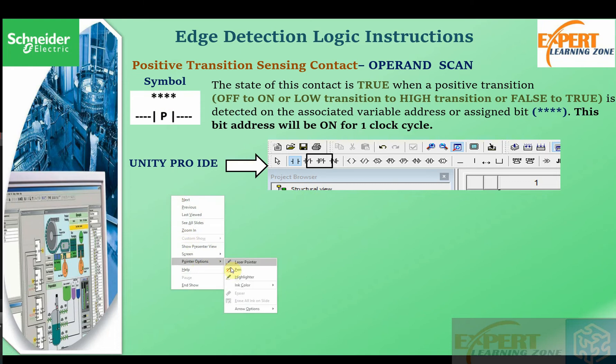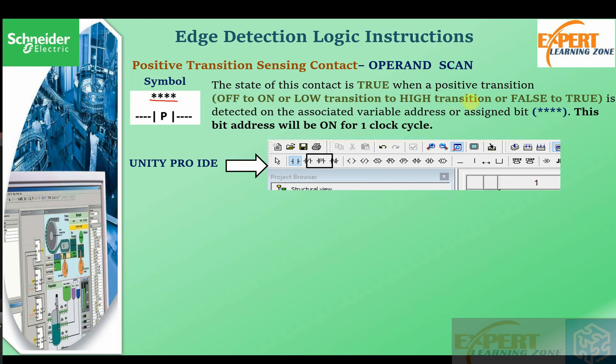To begin, we start with the positive transition sensing contact. This is the symbol — it looks like a normally open contact with a P inside, and this is the associated address. The state of this contact is true when a positive transition, that is off to on, low to high, or false to true, is detected on the associated variable address or assigned bit.